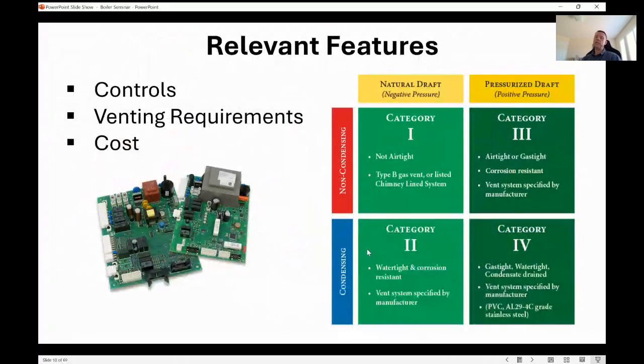So you've probably seen there are category ratings for boilers and stacks. Basically, it's divided up by whether it's a condensing or non-condensing stack, and whether it's natural draft or positive pressure. A natural draft is a negative draft system, so you're using the heat, or the buoyancy, of the flue products to create the velocity in that vent pipe in order to get those flue products outdoors. With a positive pressure stack, you're using the fan that controls the fuel to air ratio, but it is also going to push those flue products out. So you're going to need a pressurized type stack.